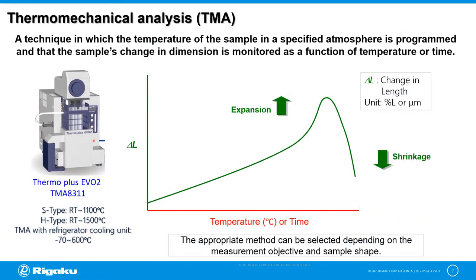Thermomechanical analysis or TMA is a technique in which the temperature of a sample in a specified atmosphere is programmed, and the sample's change in dimension is monitored as a function of temperature and time. Here is a model data of a TMA curve plotted against temperature. The vertical axis is the change in length, or delta L, quantified in percent or micrometers. An increasing TMA curve denotes expansion, while a decreasing TMA curve means shrinkage. The appropriate measurement mode can be selected depending on the measurement objective and the sample shape.